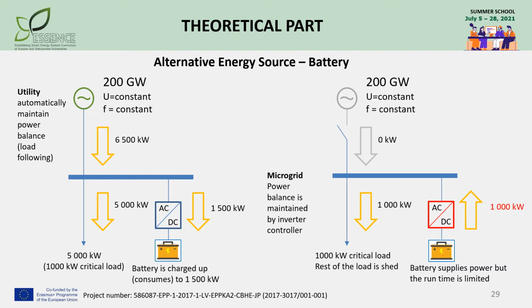Quite an evident solution to secure critical loads in case of grid outage is to install energy storage. In case of grid-connected operation, the storage charges up, which increases load consumption of the microgrid. And when the microgrid goes islanded, storage releases energy to supply critical loads. The drawback of this scheme is that energy storage has limited runtime, and the longer runtime we want to ensure, the larger capacity and higher costs are required.